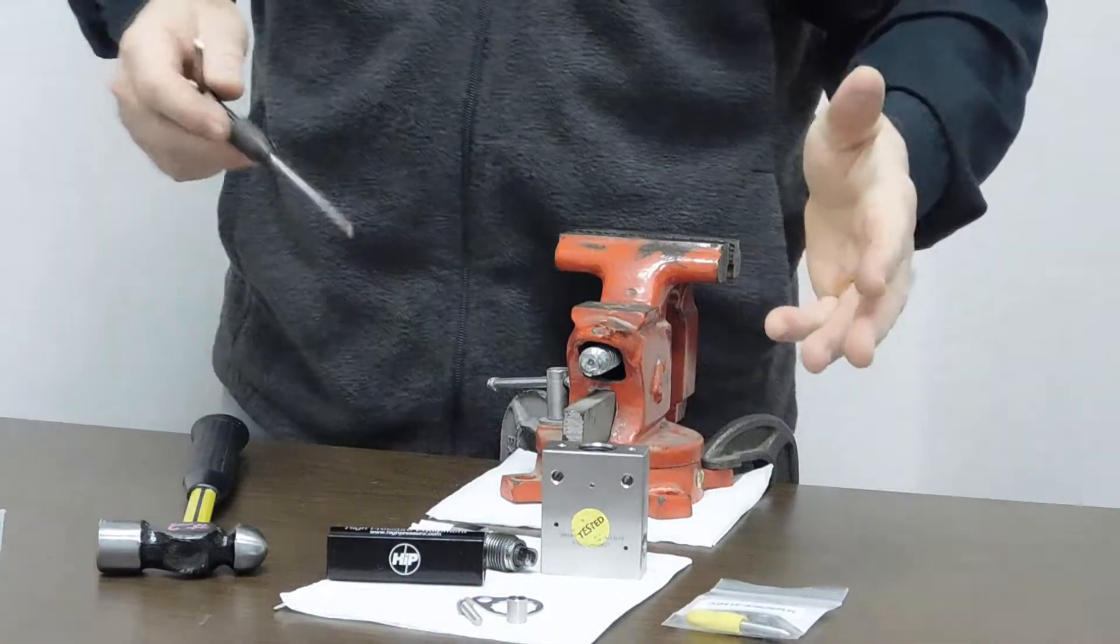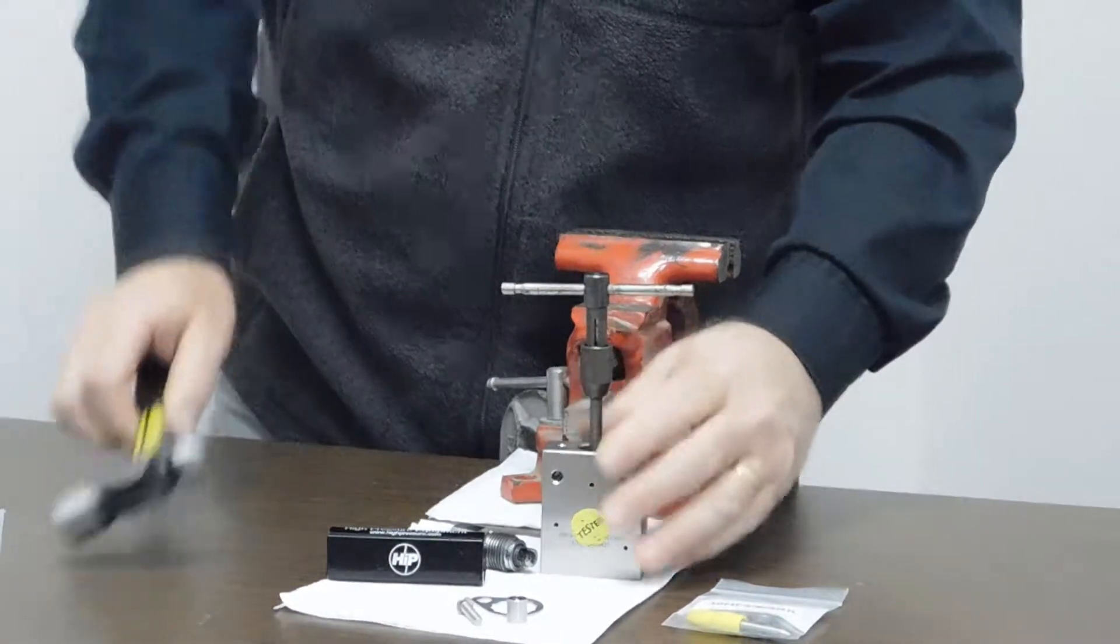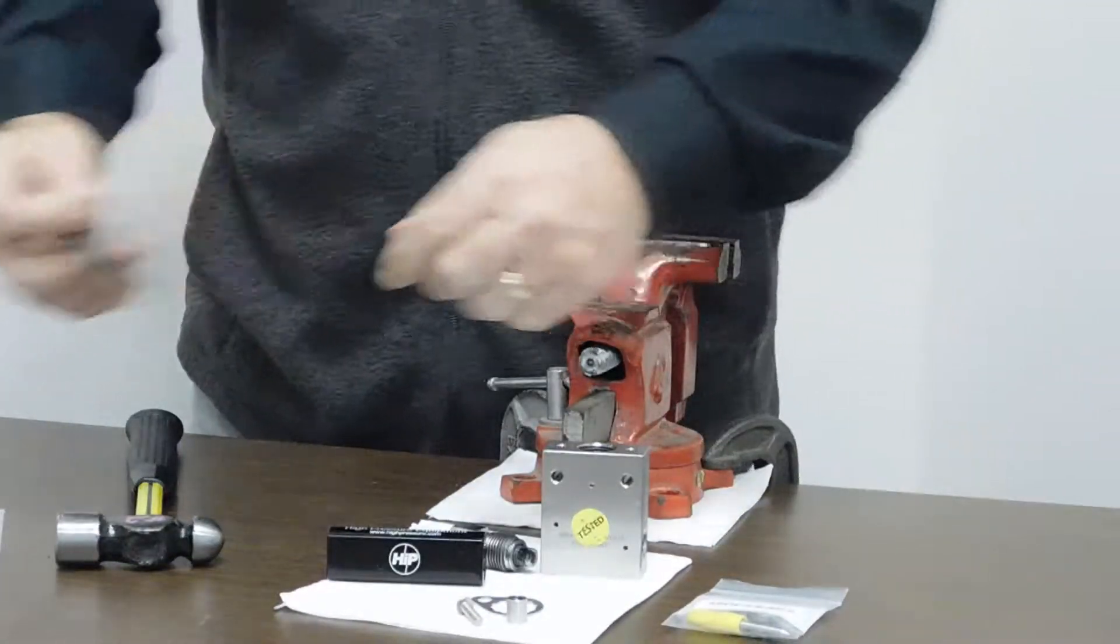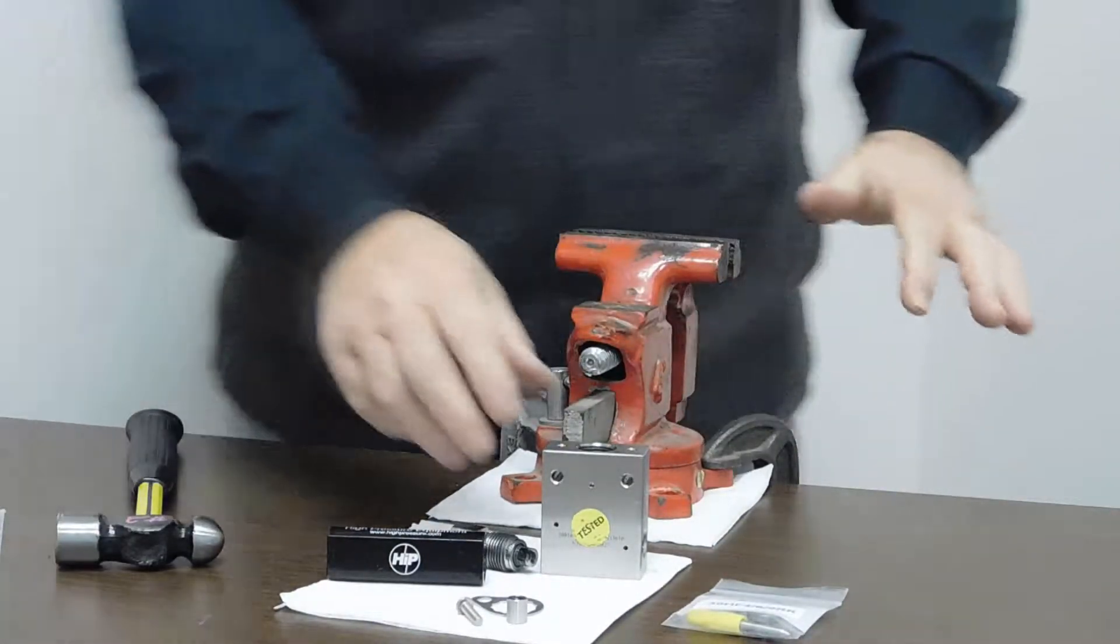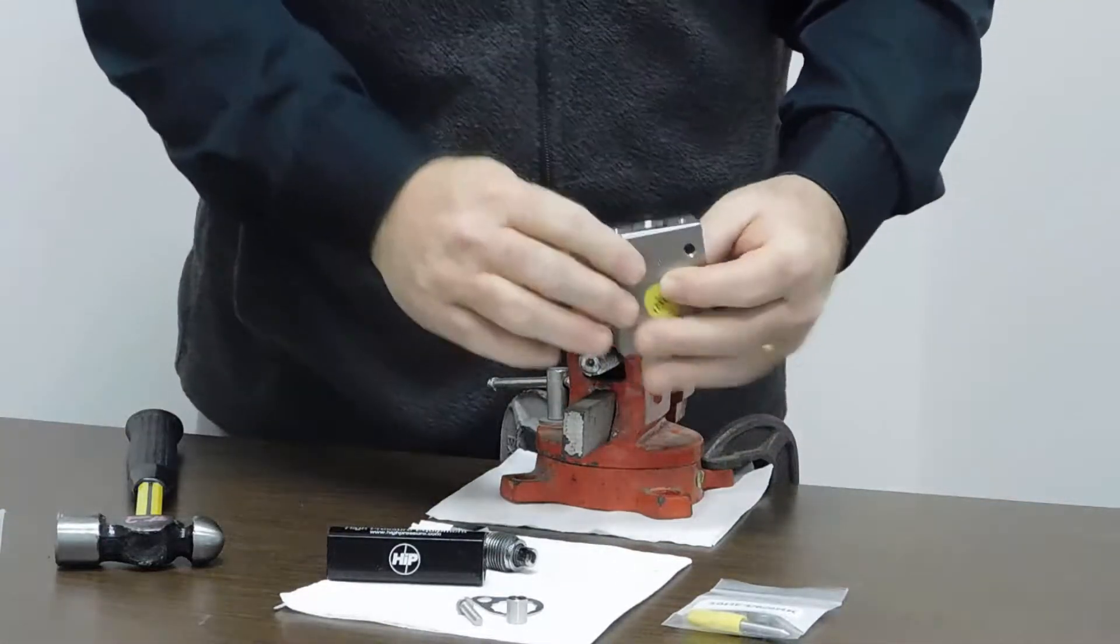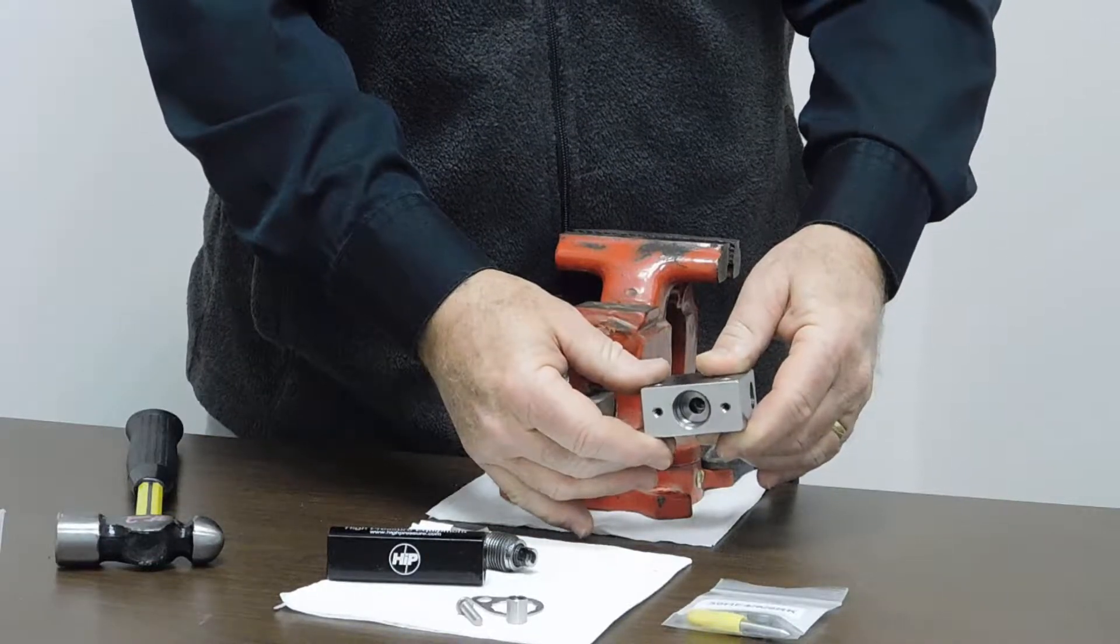The last part that comes out would be the bottom spacer. Again, just a slight tap with the hammer and that lower spacer should come right out of the body. So now our body is completely empty. We have no more packing components inside the bottom of the block. What I like to do is make sure that there's no nicks or scratches or debris down inside the valve block. This one looks pretty good.